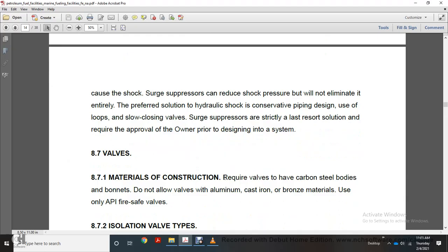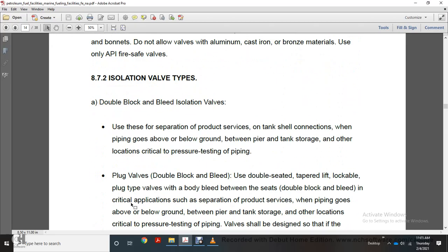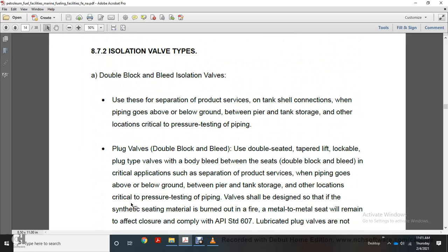Valves. Materials of construction: require valves with carbon steel bodies. Do not allow valves of aluminum, cast iron, or bronze material. Use API fire-safe valves, isolation valves, and double block and bleed isolation valves. Use these separation products over the tank shell connection wherever the piping goes to the above and below ground pier, over the tank storage, or other locations critical to pressure testing of piping.